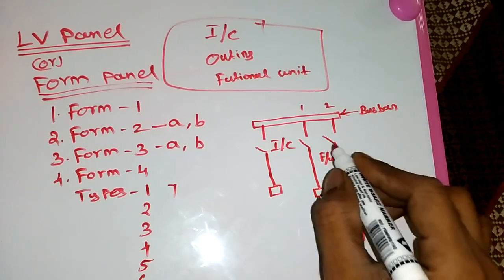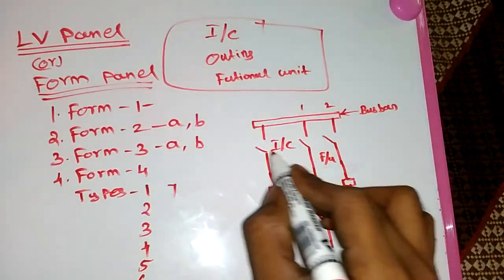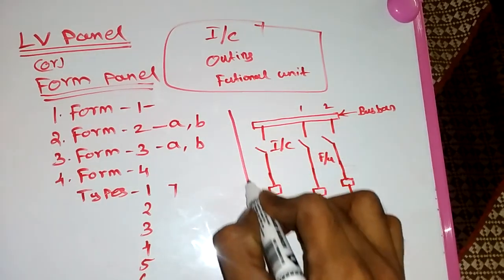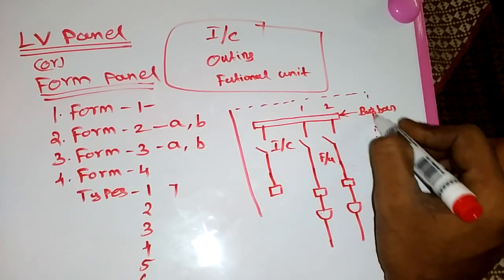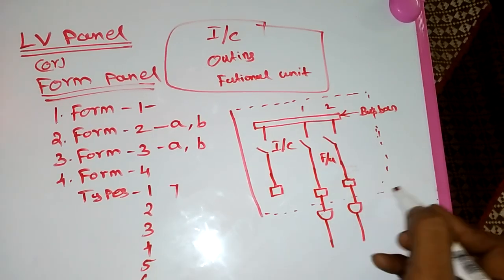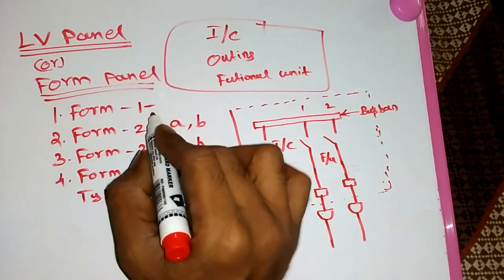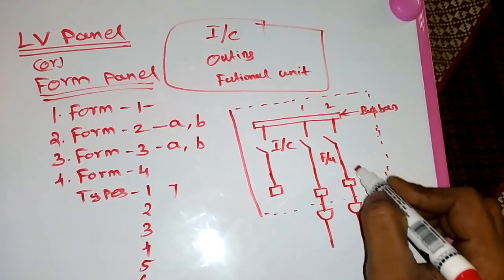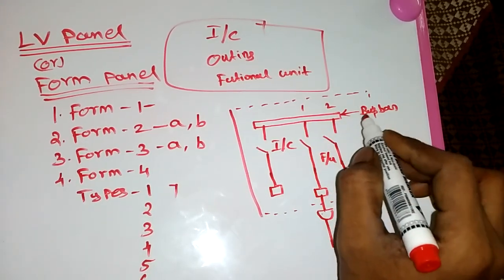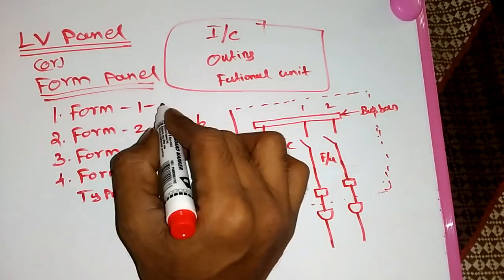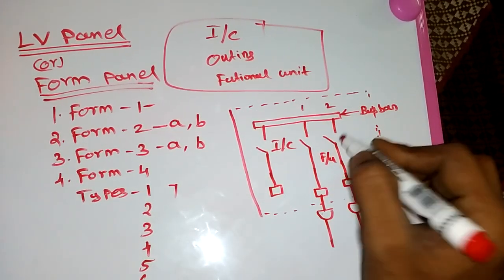This is a general diagram of LV panels. Now, how do we differentiate Form 1 through Form 4? In Form 1, everything is constructed in the same compartment — just consider this as the enclosure. The incoming, functional unit, and outgoing terminals are all kept in the same compartment — that means the same enclosure. This is called a Form 1 panel.